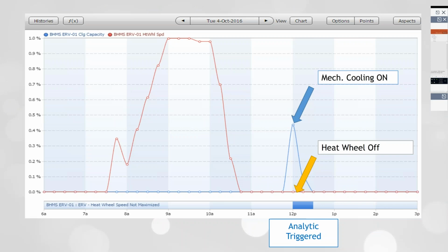So we click on that, our team dives in and trends those points to look at the information. You can see where the mechanical cooling turned on, marked with the blue arrow, and the heat wheel is off. We would have expected the heat wheel to ramp up with the cooling turning on to take advantage of that efficiency measure, and it wasn't.